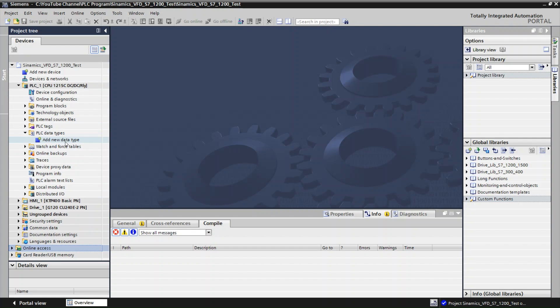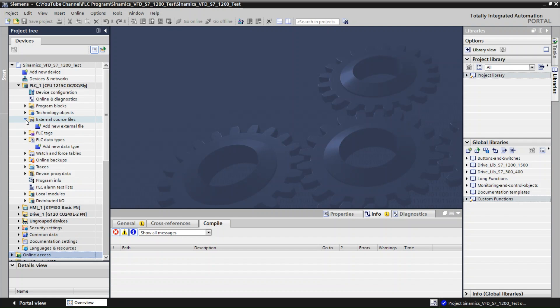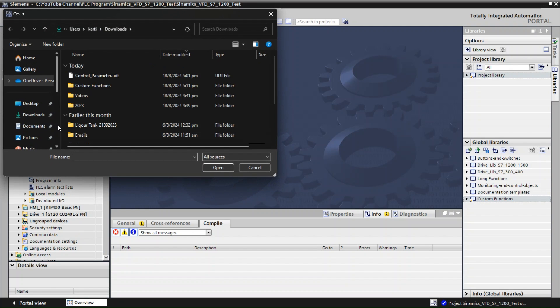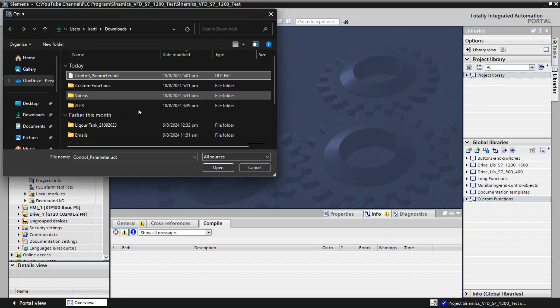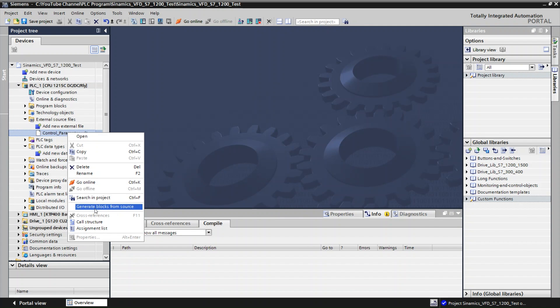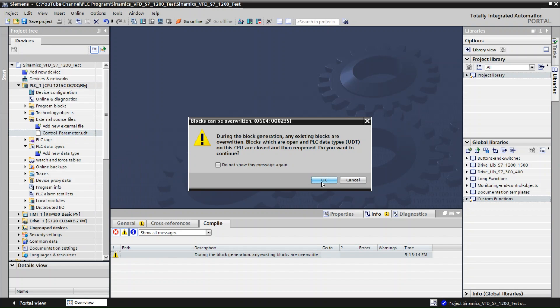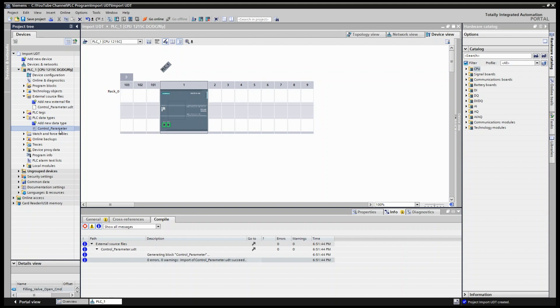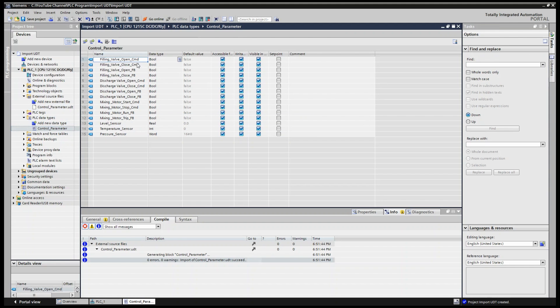To import the user-defined data type into a new project, go to External Source Files and double-click 'Add new external source file.' Browse to where you exported the UDT, go to Downloads, select the file and click Open. You can now see the control_parameter UDT has been added to the External Source Files. In the PLC Data Types folder, nothing has been added yet. Right-click on the control_parameter source file and select 'Generate blocks from source,' then click OK. Now you can see the 'control_parameter' data type has been added to the project. Double-click it to view it — all the filling valve commands, close commands, and other data types are there.